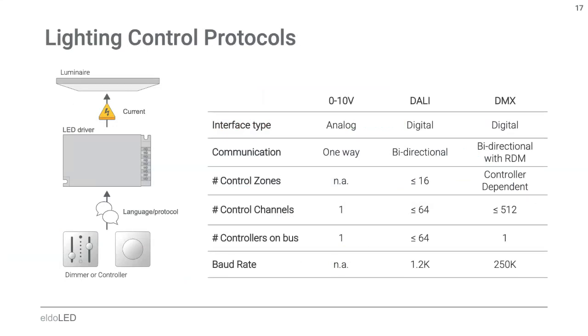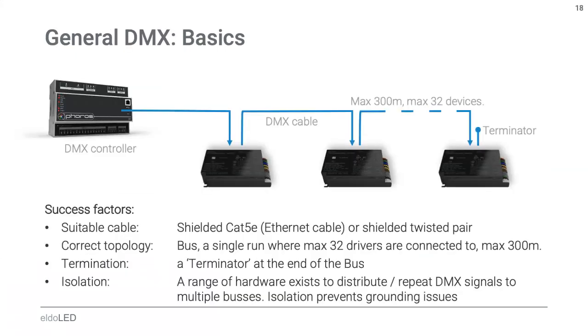From a lighting control perspective, as an LED driver manufacturer, we generate current based on the control input we receive from the dimmer or controller — that's a language, a set point. Comparing 0-to-10-volt, DALI, and DMX: 0-to-10-volt is mainly one-to-one; DALI is up to 64 LED drivers; and DMX — one single universe already contains 512 channels, with potentially many more universes. I've seen installations with 24 or 25 universes, and they're probably not the biggest out there.